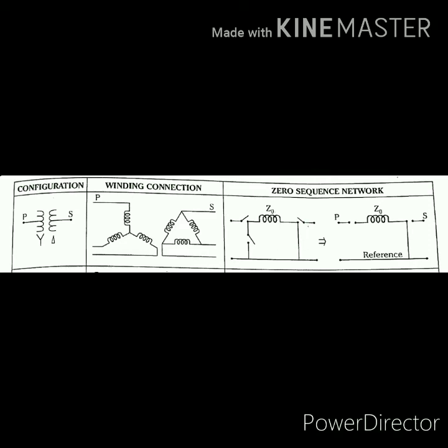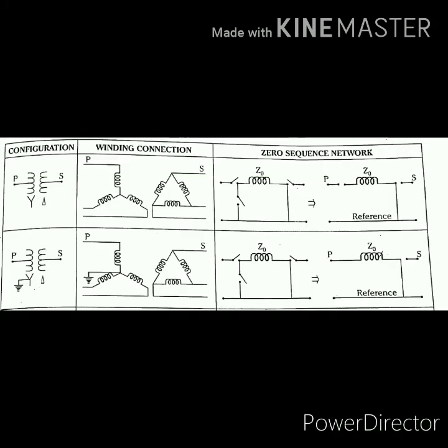So you can see the shunt switch is closed and remaining switches are open. Now see the second configuration. Primary side is star and its neutral is grounded. So when neutral is grounded, that side series switch is closed, but in the diagram by mistake they have kept it open. It has to be closed, but in the last diagram they have shorted it.